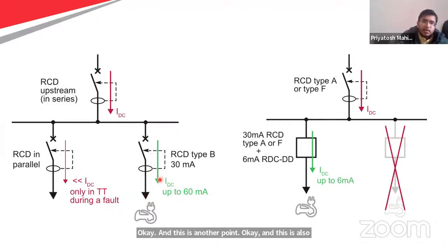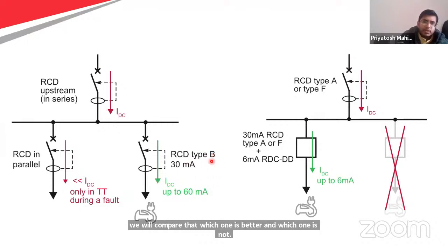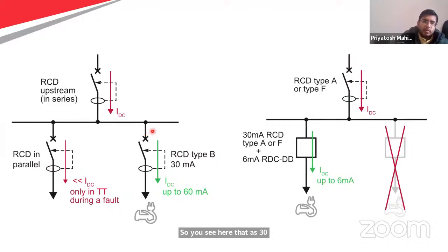Now, as I earlier told you, two types of RCDs we can use. One is RCD type B, another is RCD type A or F with RDC-DD. So these two types we will compare, which one is better and which one is not. You see here that as 30 milliamp is there, let's say two are in parallel, so we are allowing up to 60 milliamp.